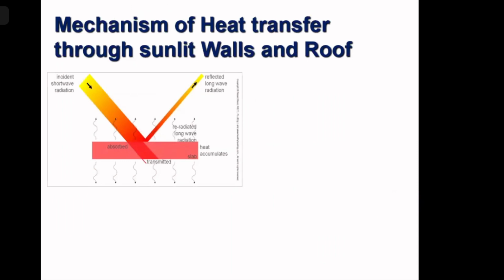Now, how does heat transfer actually occur? In our calculation, we said heat transfer equals UA delta T. But it's not that simple. We have to modify that equation a little bit. The heat falls on the wall or the roof, and some part is reflected. Then the wall or roof gets heated up. From the outside surface to the inside surface, heat flows by conduction, and the whole thing gets heated up, then it starts radiating. Some goes outside, some comes inside, and when the sun goes down in the evening, the wall remains hot and the radiation of heat still goes on.